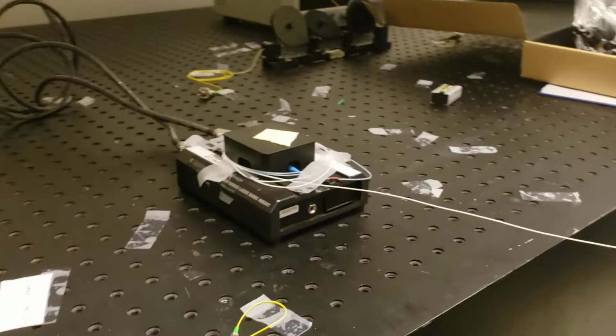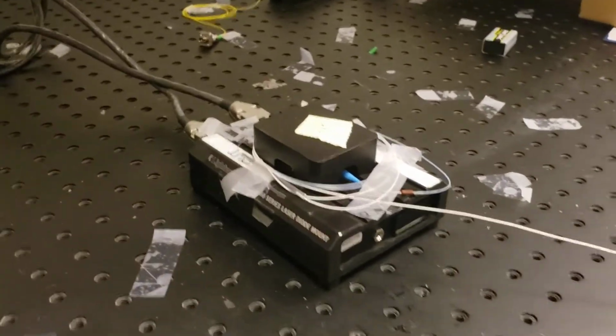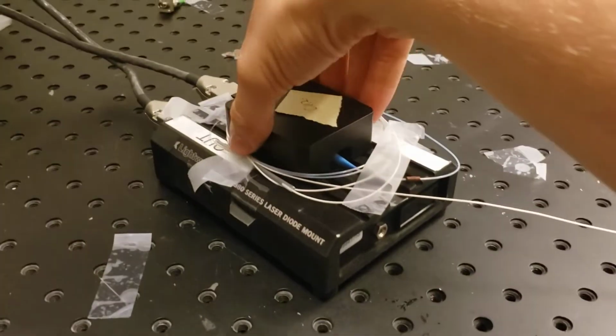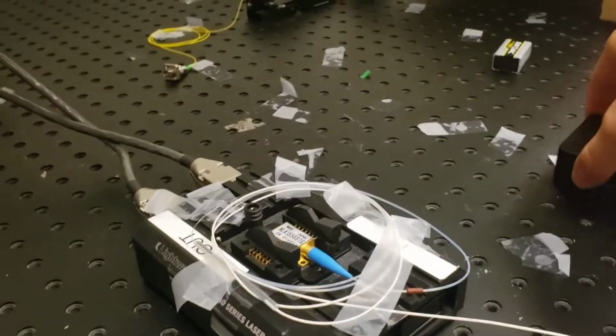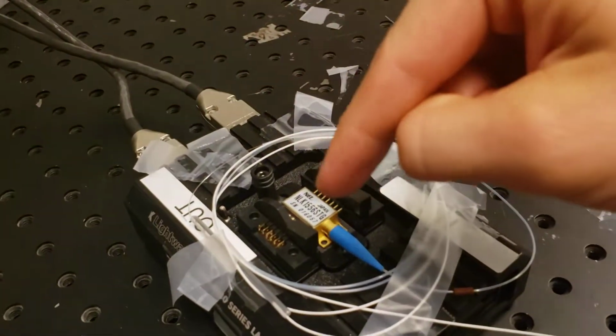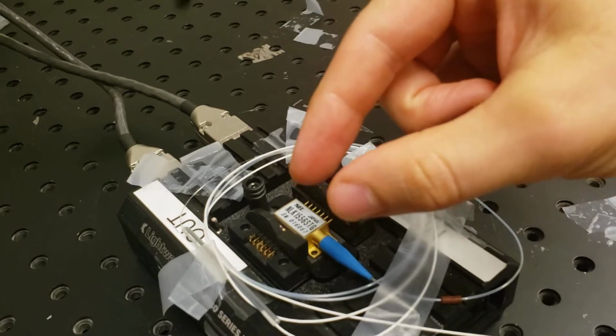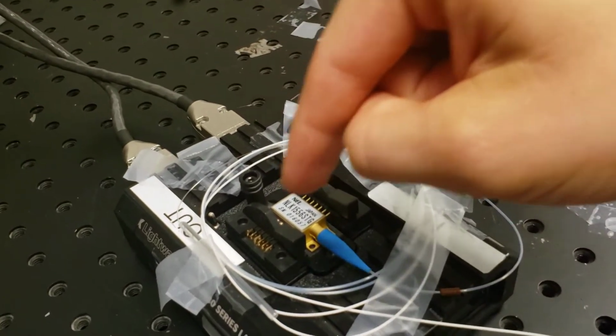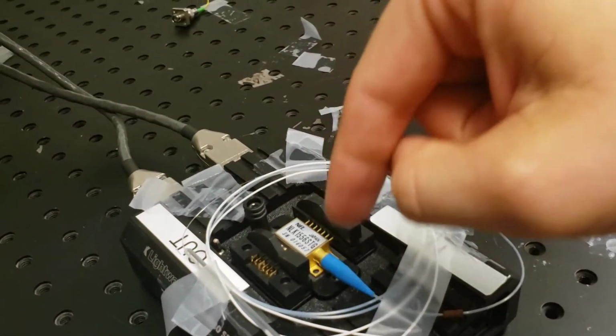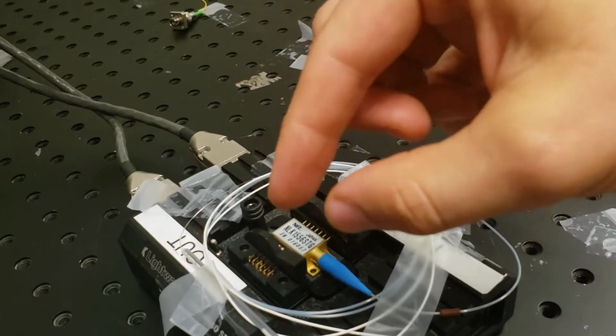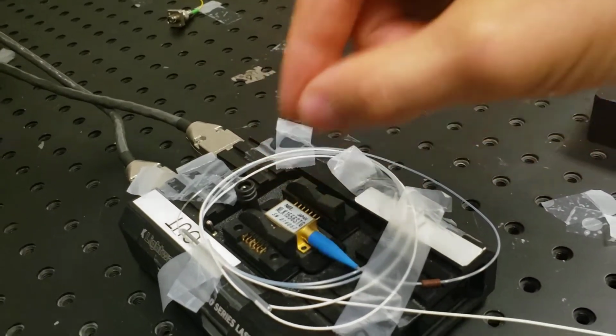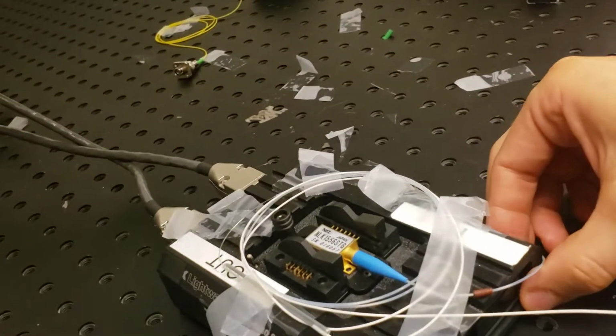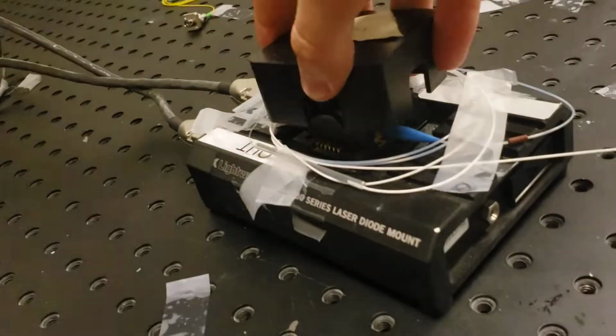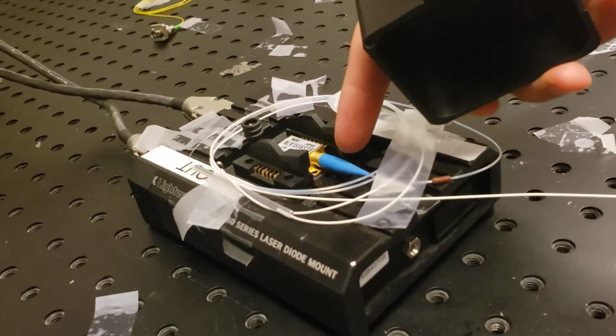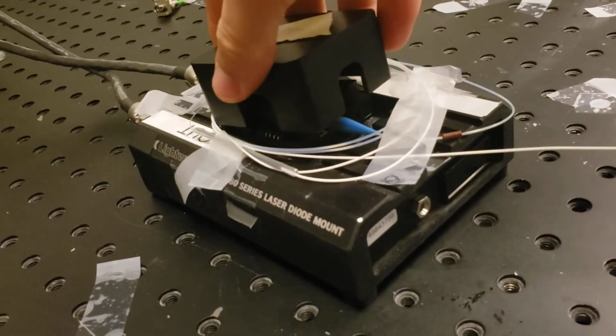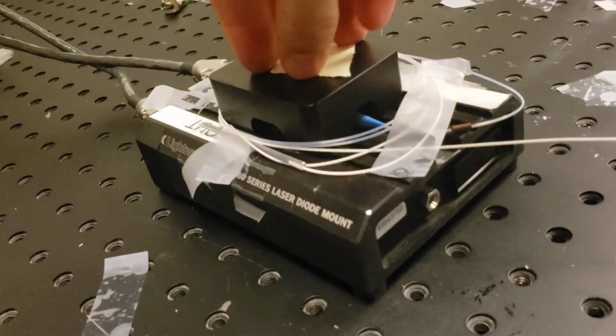And then we can show you this DFB laser right here. So in here, inside of the mounting block, we have the actual laser diode. As I explained, it essentially just consists of two mirrors, a gain medium with some periodic ridges creating a grating that ensures that only a particular wavelength gets coherently amplified. Now we keep it inside this mount both for stability and also for mechanical protection, because you can see that if you put too much weight or something drops on this output here, that's gonna really break the device, so we keep it safe in there.